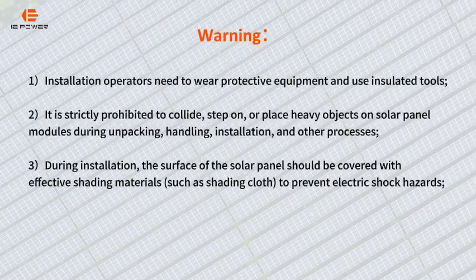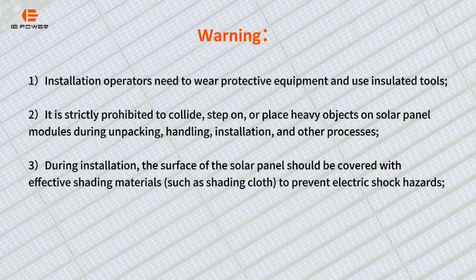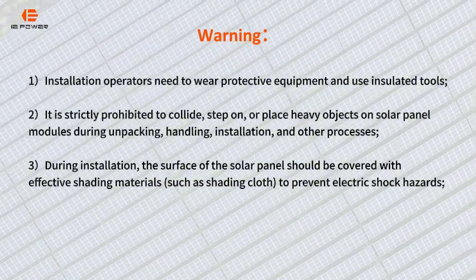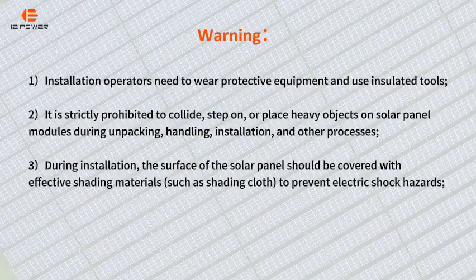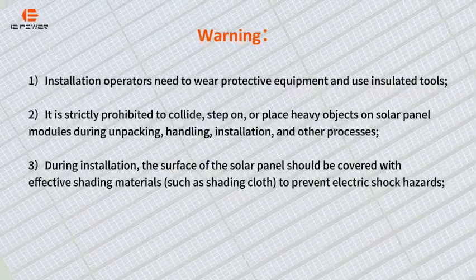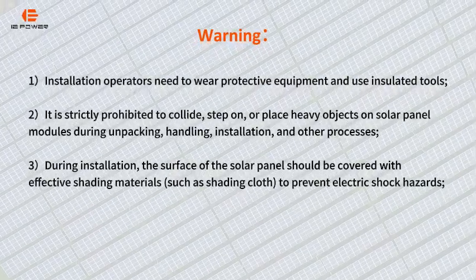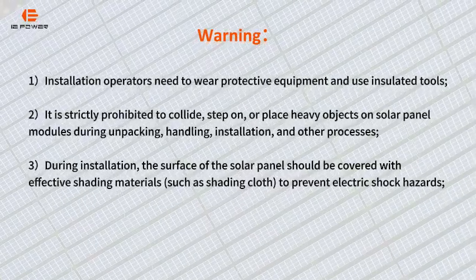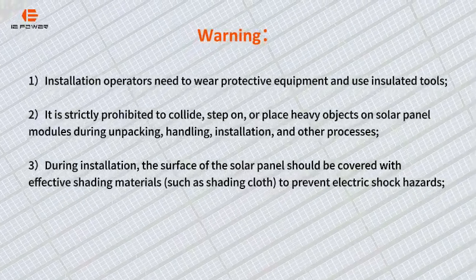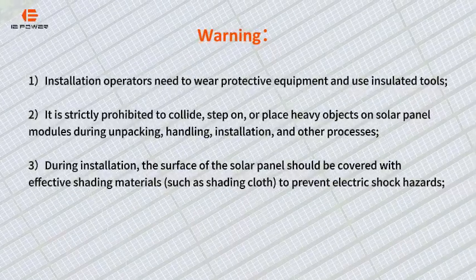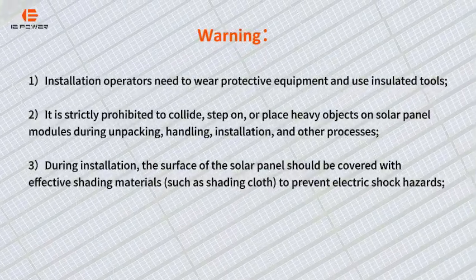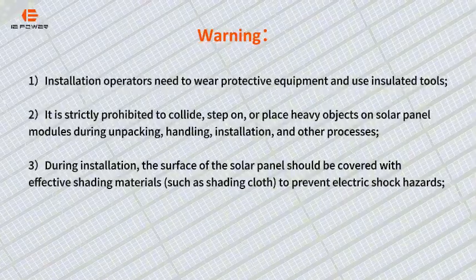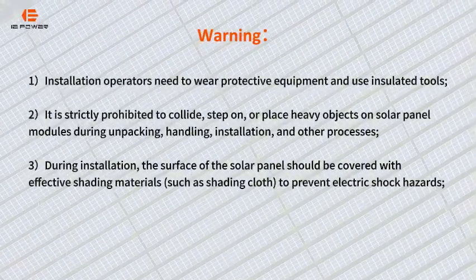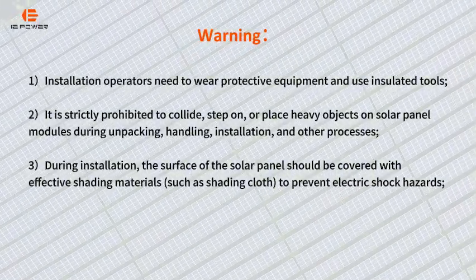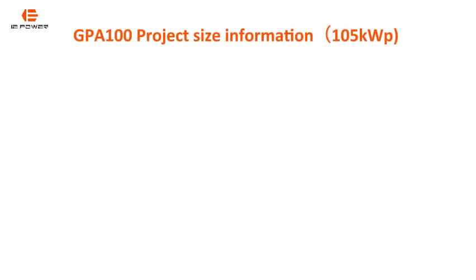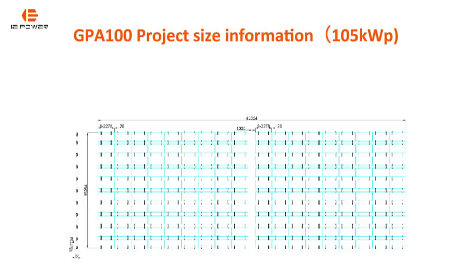Warning: 1. Installation operators need to wear protective equipment and use insulated tools. 2. It is strictly prohibited to collide, step on, or place heavy objects on solar panel modules during unpacking, handling, installation, and other processes. 3. During installation, the surface of the solar panel should be covered with effective shading materials such as shading cloth to prevent electric shock hazards. GPA100 project size information: 105 kWp.